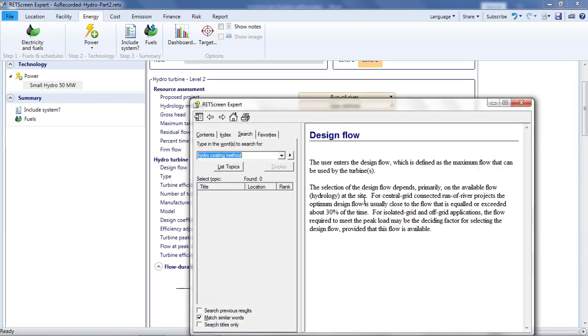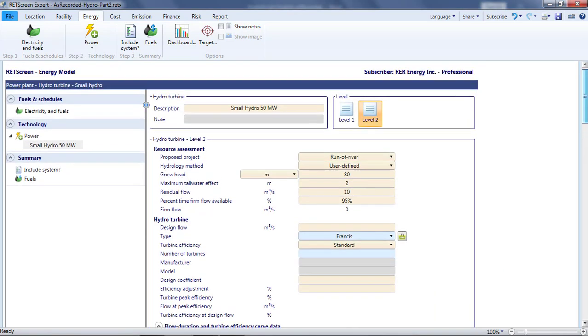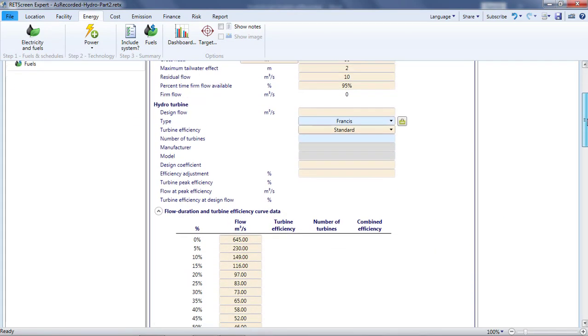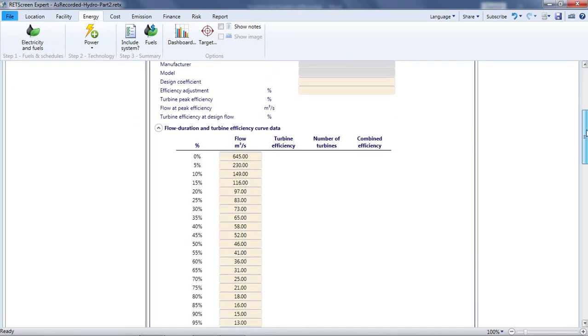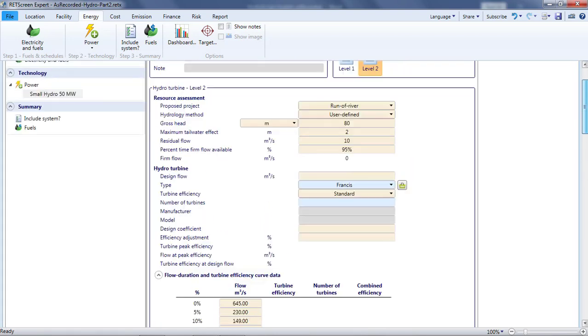I need to specify the design flow rate for my project. This is the maximum flow that the project can make use of. Beyond that, excess water bypasses the turbines. RETScreen help provides a rule of thumb. For grid-connected run-of-river projects, the design flow rate should be the flow equaled or exceeded around 30% of the time. This makes sense. If the design flow rate was bigger, then the turbine would operate inefficiently most of the time due to low flows. On the other hand, if the design flow rate was much smaller, the turbine would waste a lot of the flow. Looking at the flow duration curve, I'll pick a design flow rate of 70 cubic meters per second.